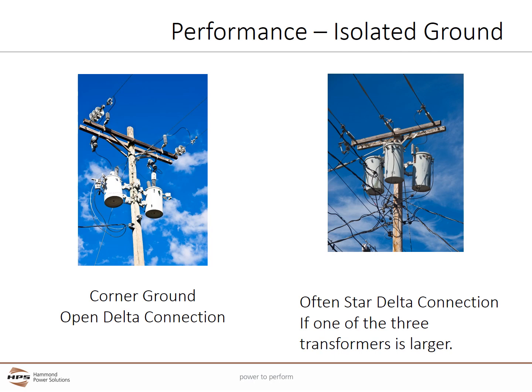Here is a good visual to look for if you are trying to evaluate if you have an isolated ground. If the facility is being powered from a transformer setup that looks like the one on the left with just 2 transformers, there's a good chance that you're using an open delta system. If the facility is being powered by 3 separate transformers and one of those 3 cans is larger than the other 2, in this case all 3 cans are the same size, but if one of those 3 cans is larger, often you'll be powered by a star delta connection.